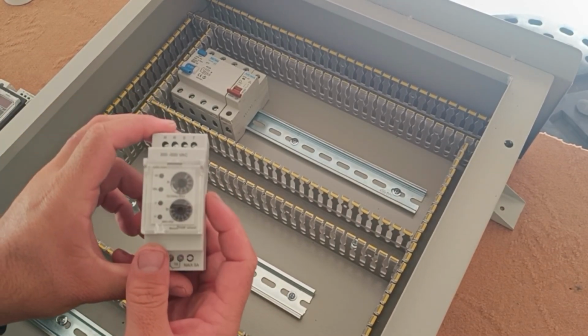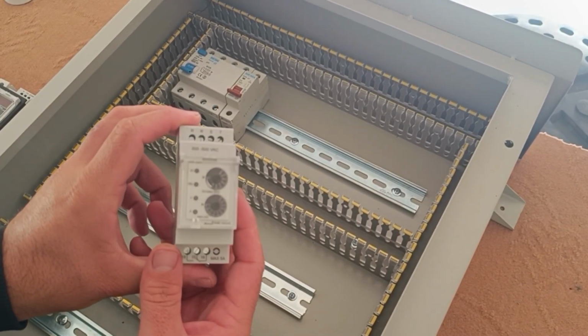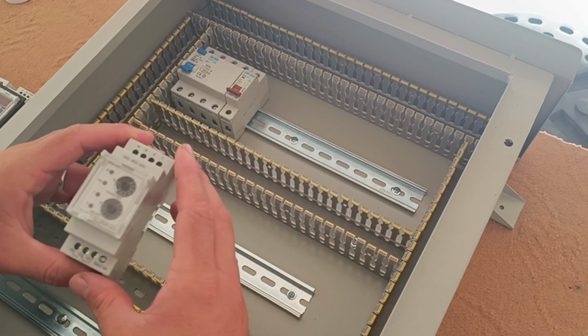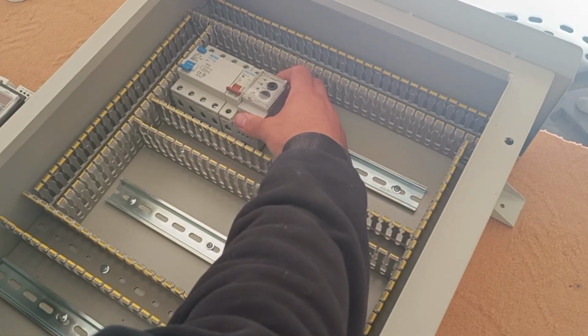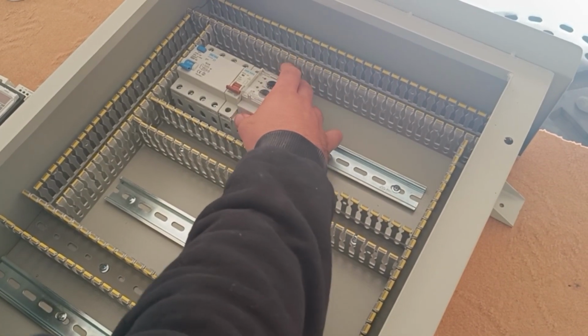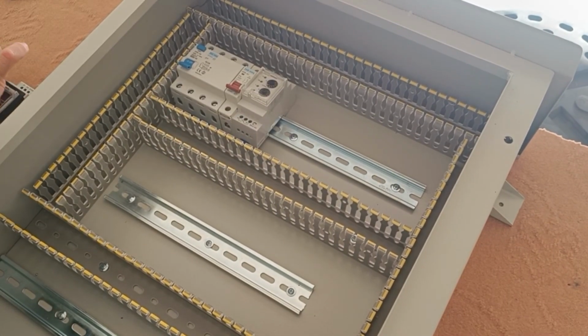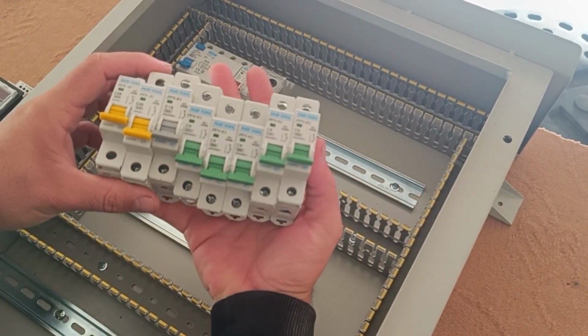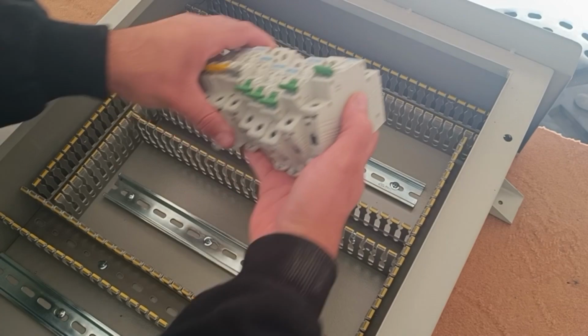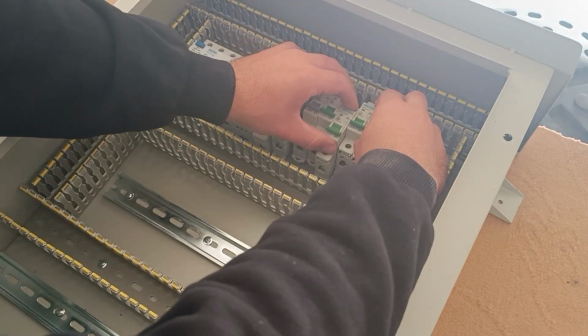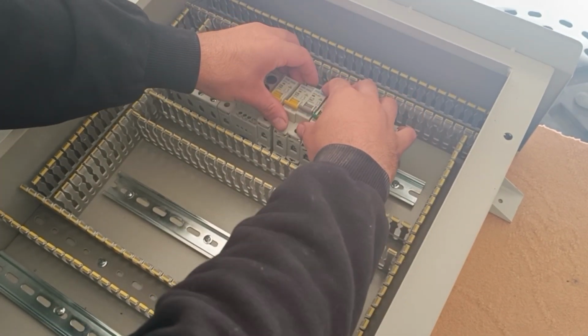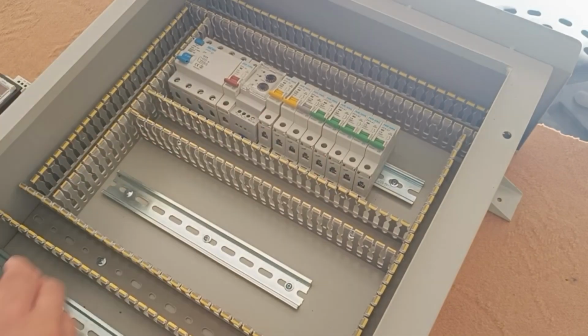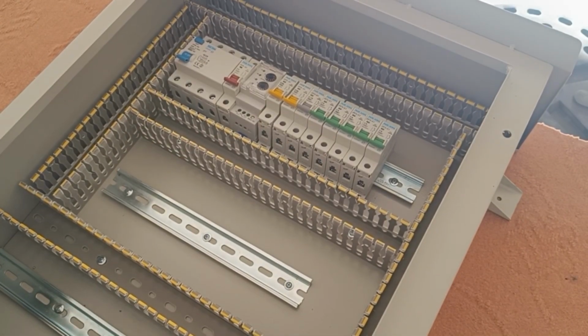This is a phase voltage control relay designed for protecting the circuit against phase loss. The wiring introduction will be provided shortly. This electrical panel has several single-phase outputs, for each of which we use a single-phase miniature switch. These miniature switches protect the circuit against short circuit.